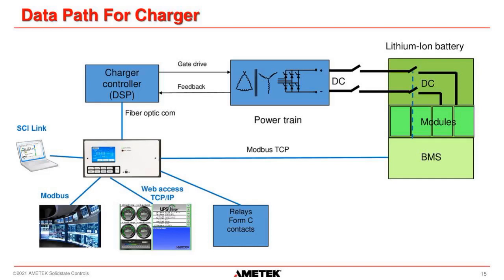So when we connect to the lithium-ion battery, this is how the data path goes. In the center left, we have our HMI for our UPS. That connects to the battery directly via Modbus TCP, and the HMI on the UPS pulls data from the battery at certain intervals. The HMI also connects to our charger controller inside the UPS, and so the values that are acquired from the lithium-ion battery are then forwarded onto the charger. So the charger can regulate to the voltage and current that the battery is requesting. So we never are going to go over the maximum voltage or current that the battery can handle.